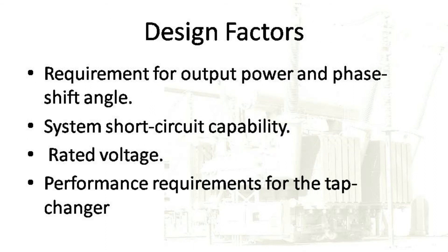In reality, phase shift transformers can be built in different designs and different compositions. However, the key design considerations that would be affected are: number one, the requirement for the output power and phase shift angle; number two, the system short circuit capability; number three, the rated voltage that you need; and lastly, the fourth design factor will be the performance requirements for your transformer tap changer.